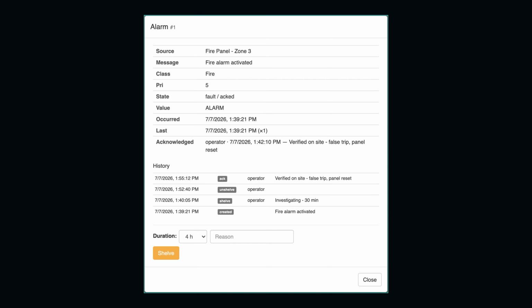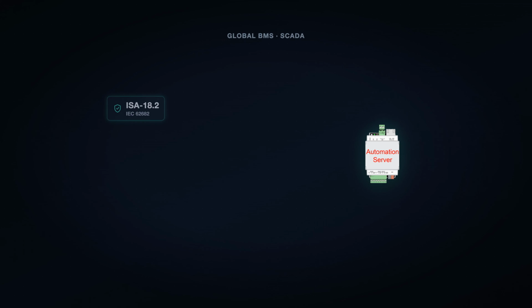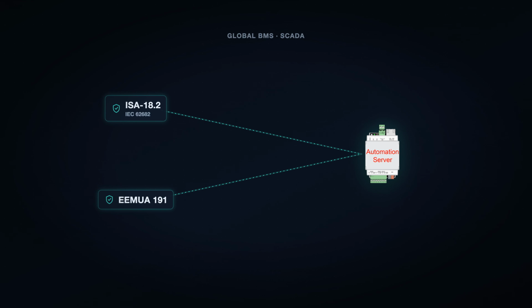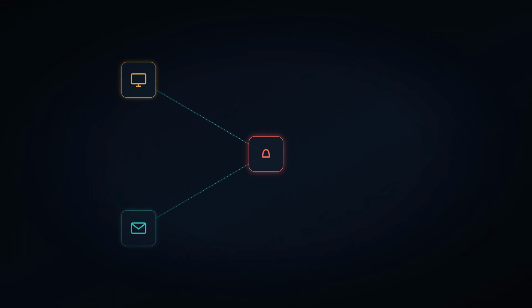Every acknowledgement is written, together with the acknowledging user, the time of the action, and, where the class requires it, a mandatory operator note into an audit record that cannot be altered afterward. In this way, Alert Plus brings the alarm discipline that global BMS brands treat as standard, the principles of ISA 18.2, IEC 62682, and EEMUA 191 onto the automation server. A critical situation is both seen and heard on screen. Because only the highest priority alarm sounds at any one time, there is no noise pollution.